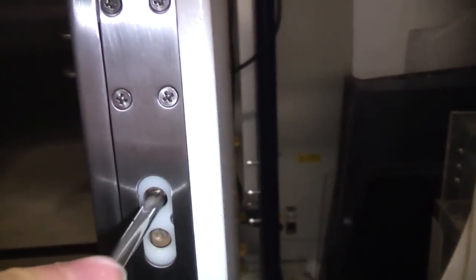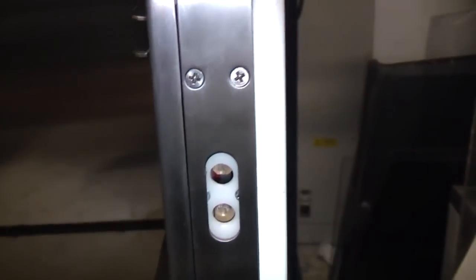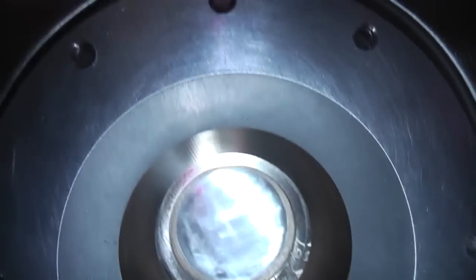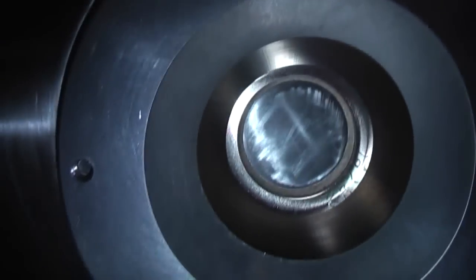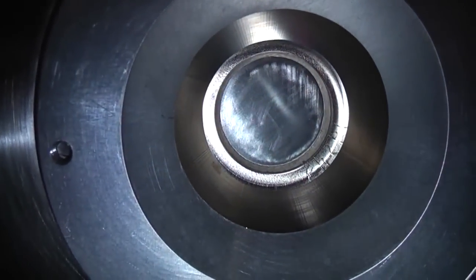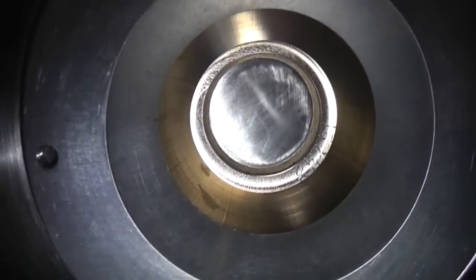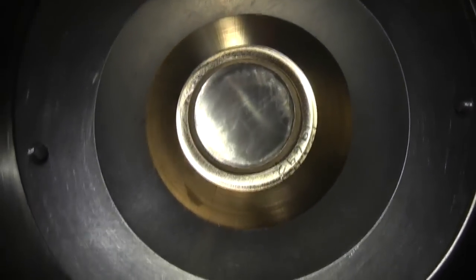Right, so inside the cabinet we've got this double interlock thing which contacts these 2 micro switches to make sure it turns off when you open the door. That's the actual aperture where the X-rays come out. That will be a beryllium foil window, which is somewhat fragile. You certainly do not want to be poking your fingers at that.